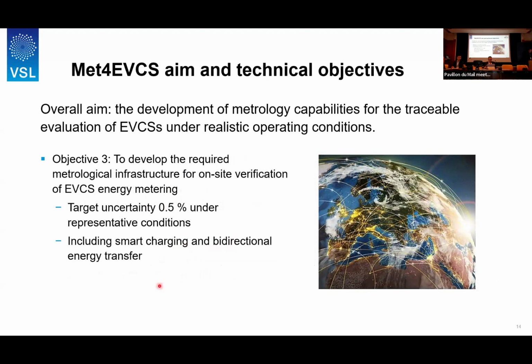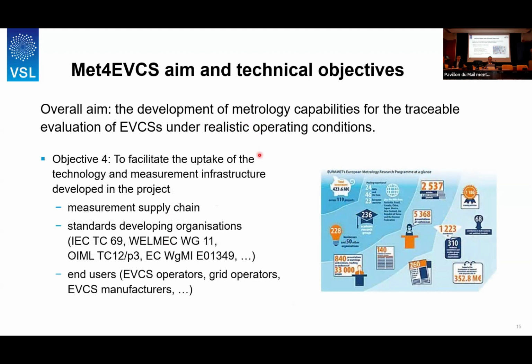The third objective is to develop the required metrology infrastructure for on-site verification. So that's a bit more difficult, and therefore we aim for an uncertainty of 0.5%. And that includes smart charging and bidirectional charging, so also the EV feeding the grid instead of the other way around. And there's always the fourth impact objective, which I want to mention. That's to facilitate the uptake of the technology and the developments, and also of the measurement infrastructure that is developed, and to communicate that to the users. And in that case, that's the measurement supply chain, but also standardization committees like IEC TC 69 and also TC 13 about metering, and WELMEC working group, OIML technical committee, and the European Commission working group that's responsible for the MID.